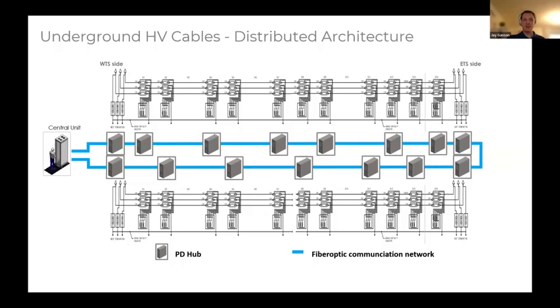And those splices and the terminations are the most common points of failure on a cable. And so when you think of a splice and we think about overall budgets for this type of thing, it's important to realize that, when we're looking at a splice, a planned replacement is often around the cost of $60,000. And that's for a planned replacement. When we have failures on underground cables, I think the average is 4 to 9 days because of locating the failure, replacing the cable, replacing the splices. So these underground assets are something that we really want to take care of and monitor in as much real time as we can. And so the architecture that we proposed was putting in partial discharge monitoring at both of the terminations and also inside all of the splice vaults.